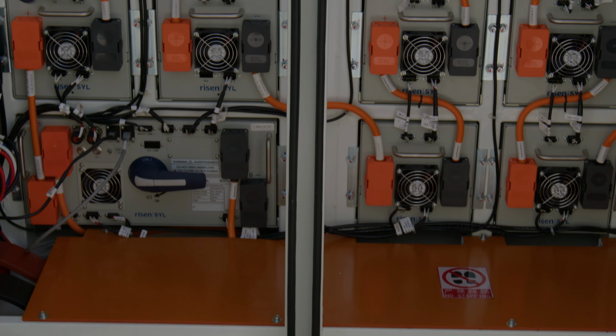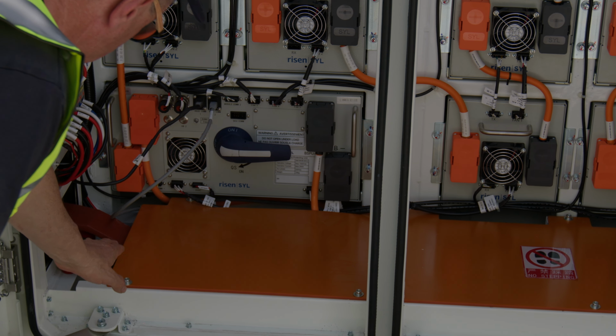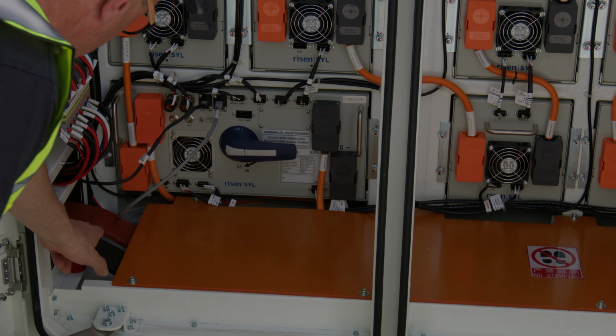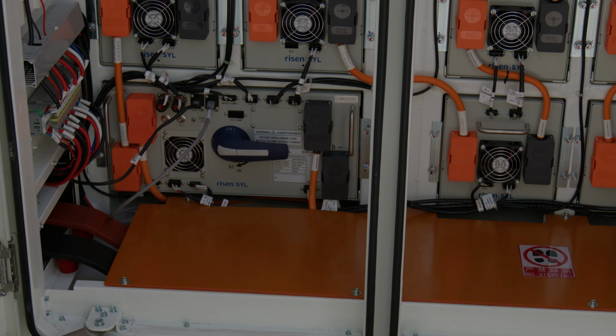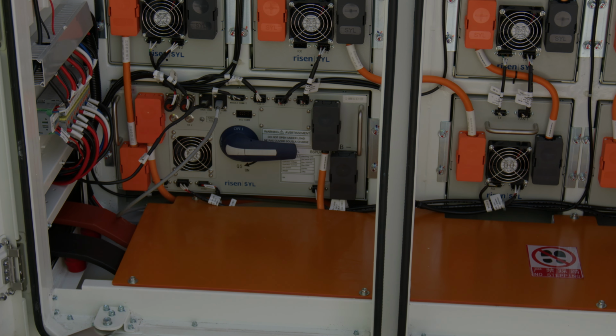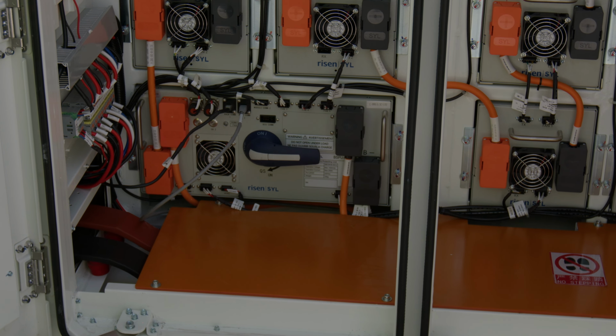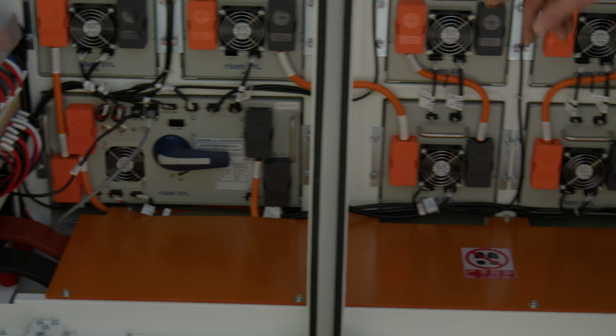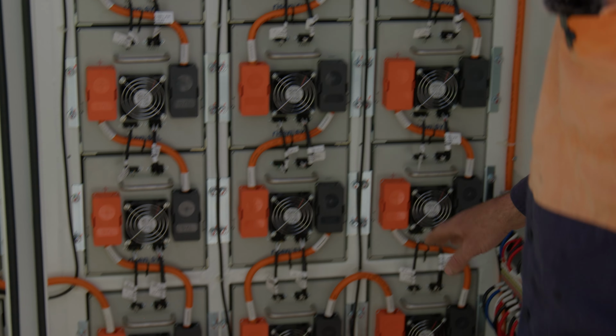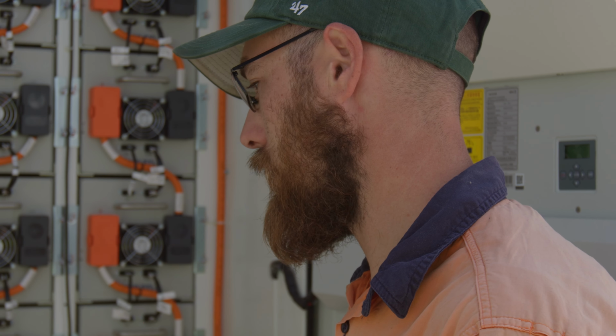And you can see here that unbroken bus bar that Alex was talking about, running from the cabinet we just spoke about before. Yeah, so they run from the battery connection panel through to the first battery, then out to the second, and then so on to the third, fourth, however many batteries you have. In this case, we have 3 per battery connection.